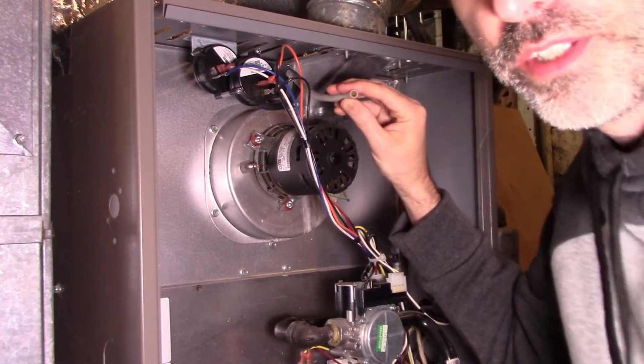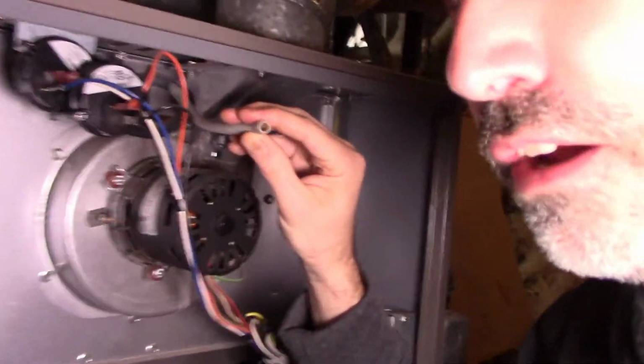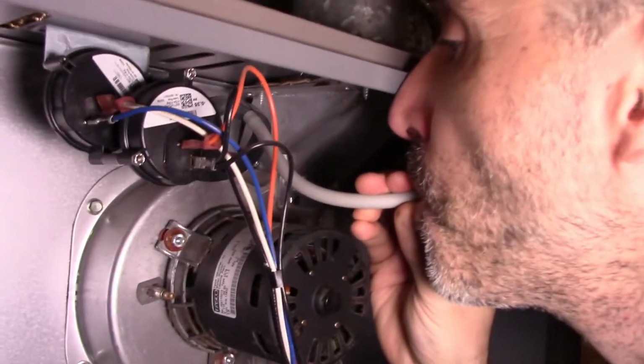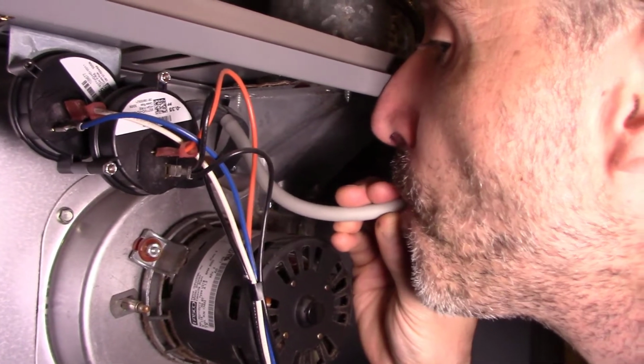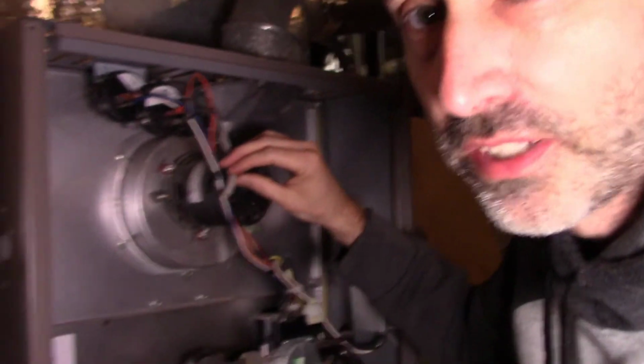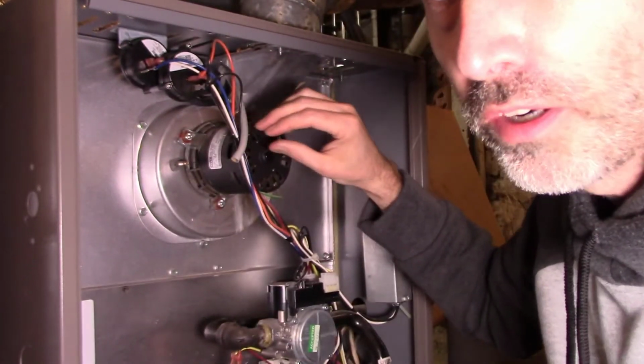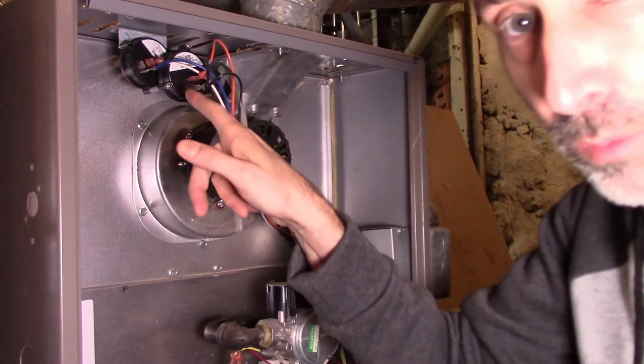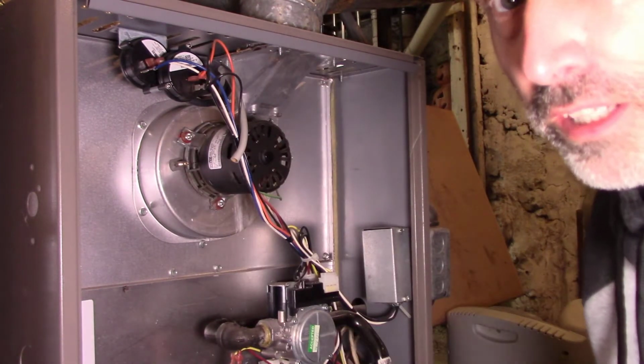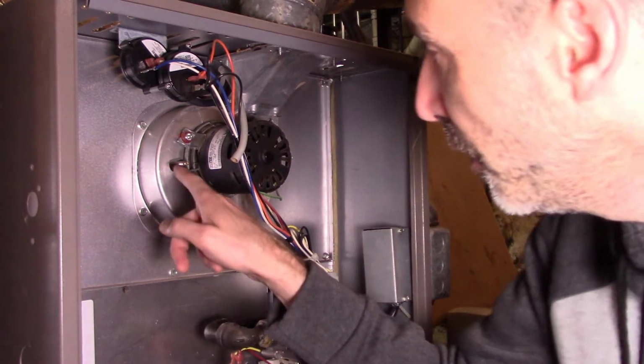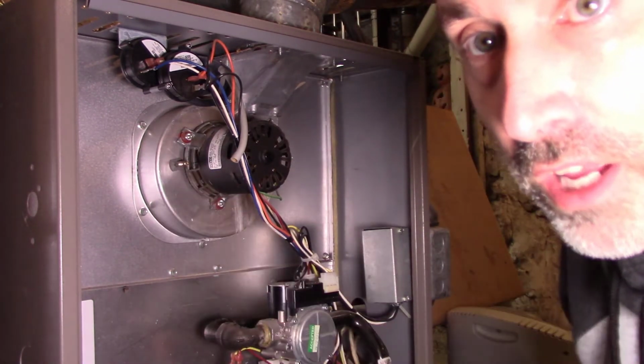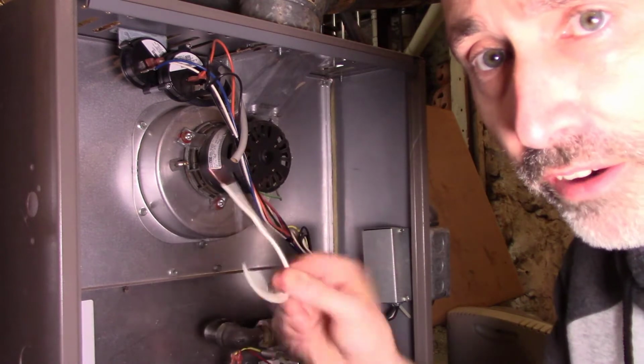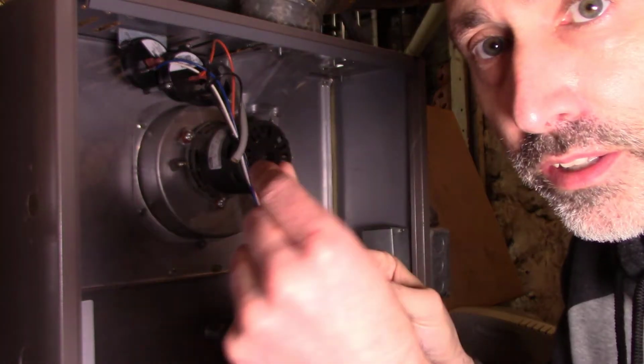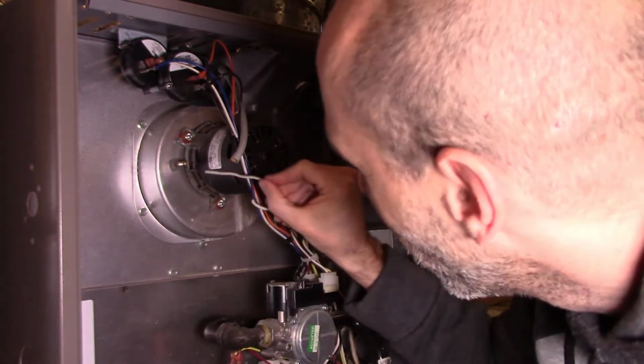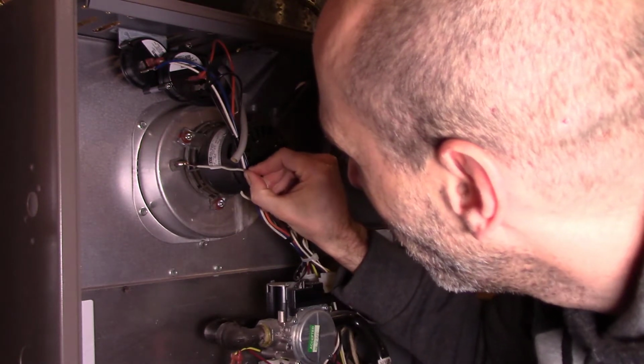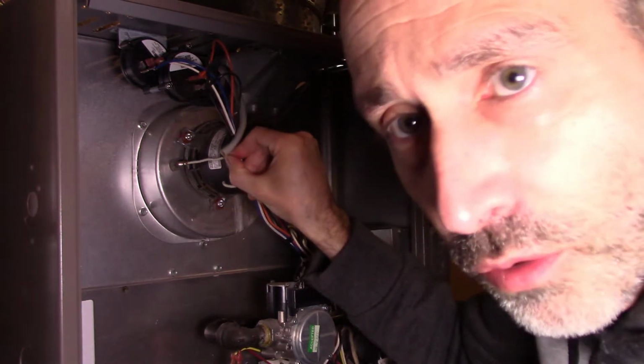You hear that? Let me see if I can get the camera real close so I can get the audio. When I suck on it, I hear those switches clicking, which tells me they're probably working. But usually the problem is not with the pressure switch failing, although it certainly can be, but it's usually this port, like I said, this port getting clogged. So what I like to do is take a little piece of wire or anything thin enough that I can get in there. And notice, you'll hear it. Actually, it really needs to be cleaned because I hear crunchiness in there.